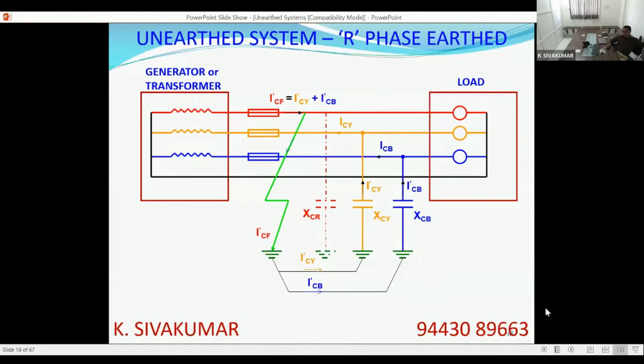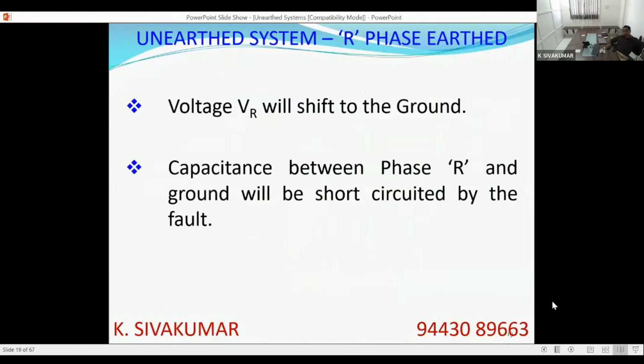But you can see for XCY, the ground side plate will now be impressed with the R phase voltage. Earlier it was the neutral voltage, or zero voltage. Now it will be impressed with the R phase voltage. So also for XCB. So the capacitances XCY and XCB will receive line voltage and not phase voltage under this condition. That is what is explained here.